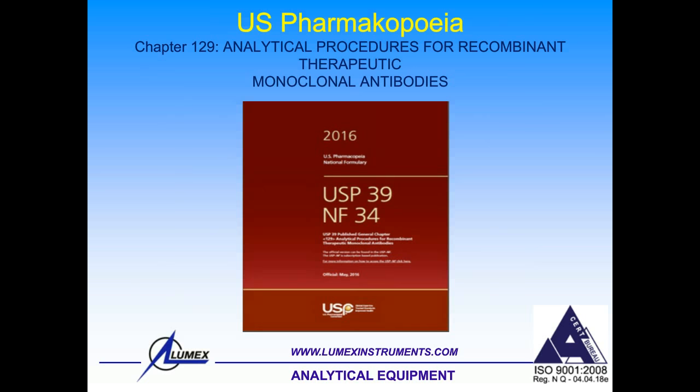For United States Pharmacopeia, the general article about CE has been existing for quite a long time, but only last year in 2016 a special chapter 129 appeared — 'Analytical Procedures for Recombinant Therapeutic Monoclonal Antibodies.' In this chapter it is clearly stated in all details how capillary gel electrophoresis can be used for the determination of recombinant therapeutic monoclonal antibodies of the IgG class, and how we use these prescriptions on our instruments.